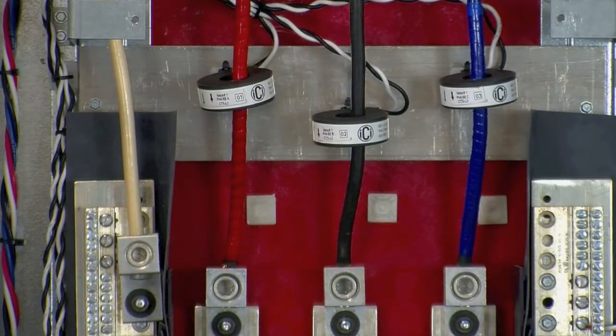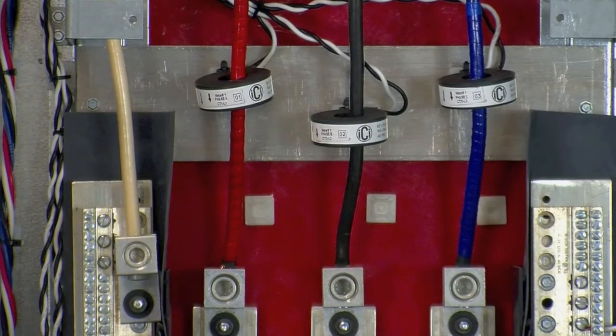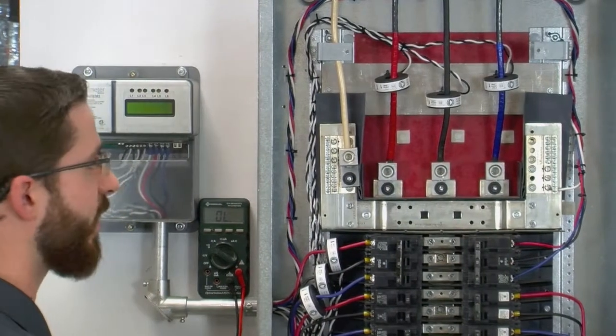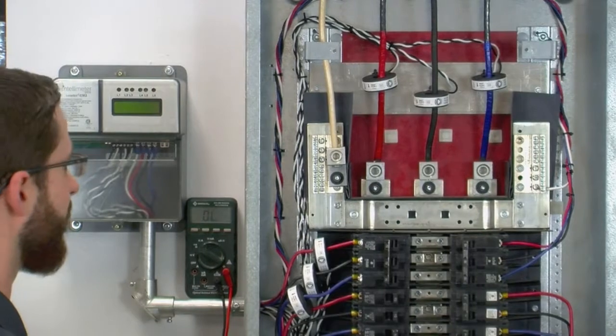So our CTs to meter the main load are now in place. If we wanted to meter a breaker load, a phase test would be required. To check the phasing of a panel that is not yet energized, you will have to rely on a continuity test.